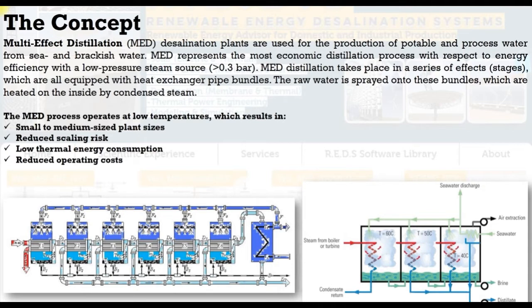MED distillation takes place in a series of effects or stages, which are all equipped with heat exchanger pipe bundles. The raw water is sprayed onto these bundles which are heated on the inside by condensed steam. MED process features include: relatively low operating temperatures, small to medium plant sizes, relatively low specific power consumption, low scaling risk, low thermal energy consumption, and reduced operating costs.